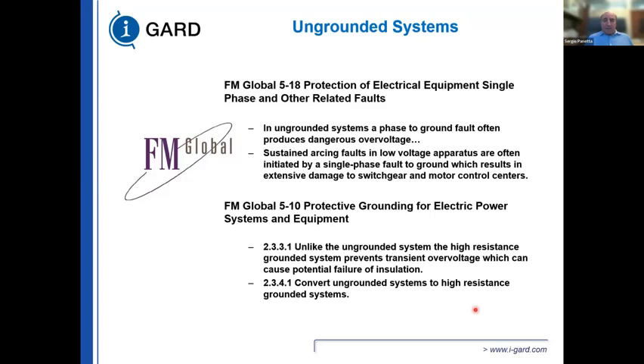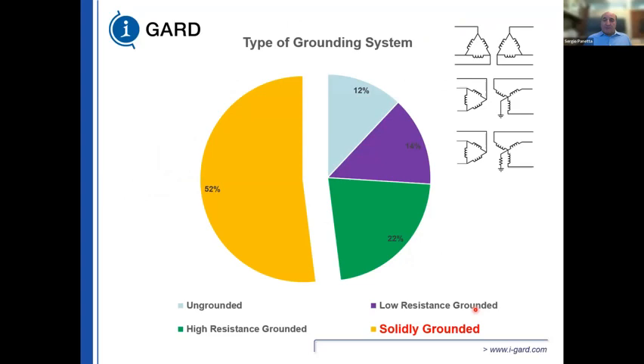Unlike an ungrounded system, high resistance grounded systems prevent transient overvoltage. So this is FM Global's way of saying, okay, ungrounded systems are bad, let's move to something else. And the easiest thing to do from an ungrounded system is transition to a high resistance grounded system, depending on the system voltages. For sure, if you have a low voltage system under 5 kV, you can transition to a high resistance grounded system very easily. So their recommendation is to convert an ungrounded system to a high resistance grounded system.